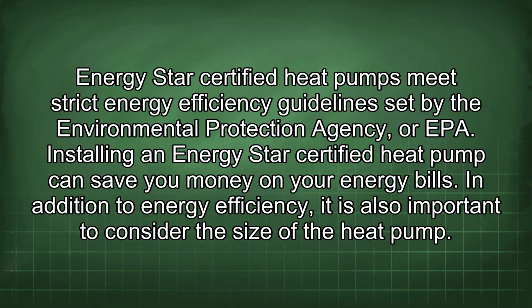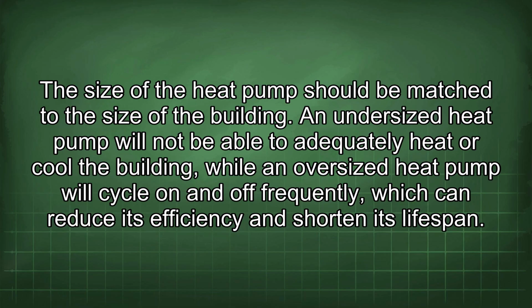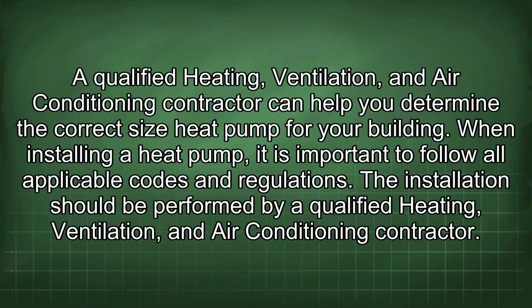In addition to energy efficiency, it is also important to consider the size of the heat pump. The size of the heat pump should be matched to the size of the building. An undersized heat pump will not be able to adequately heat or cool the building, while an oversized heat pump will cycle on and off frequently, which can reduce its efficiency and shorten its lifespan. A qualified heating, ventilation, and air conditioning contractor can help you determine the correct size heat pump for your building.